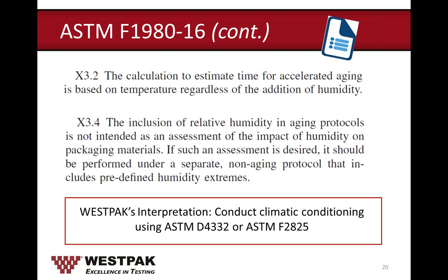The second change is section X3.4: the inclusion of relative humidity in an aging protocol is not intended as an assessment of the impact of humidity on packaging material. If such an assessment is desired, it should be performed under a separate non-aging protocol that includes predefined humidity extremes. WESTPAK's interpretation is to conduct climatic conditioning using ASTM D4332 or ASTM F2825.